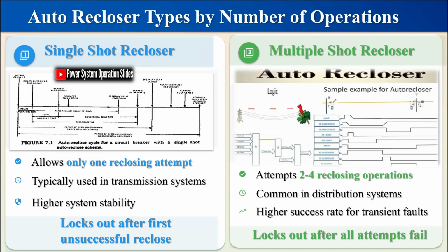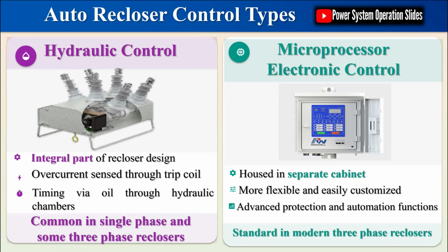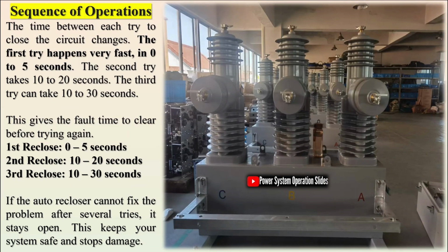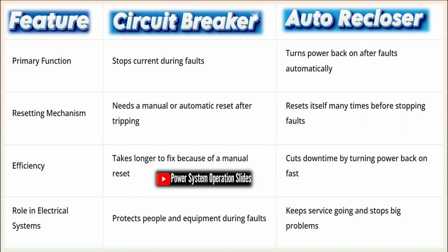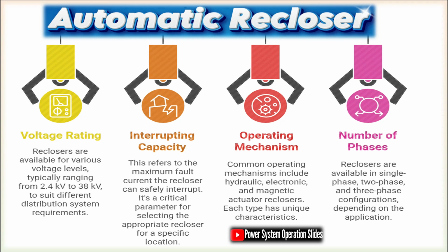4. Result evaluation. If the line successfully recovers, it means the fault was indeed transient, and power supply is quickly restored without manual intervention. However, if the fault is permanent, e.g., a fallen pole or broken line, the recloser's first attempt will fail, and the protective relay will trip again. 5. Lockout. In cases of permanent faults, the recloser device enters a lockout state, discontinuing further reclosing attempts and awaiting maintenance personnel intervention. This intelligent mechanism effectively distinguishes between transient and permanent faults, avoiding repeated stress on equipment due to persistent faults while maximizing power supply continuity.